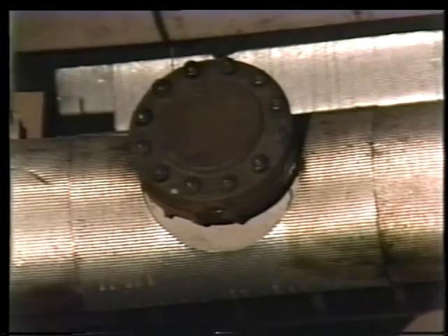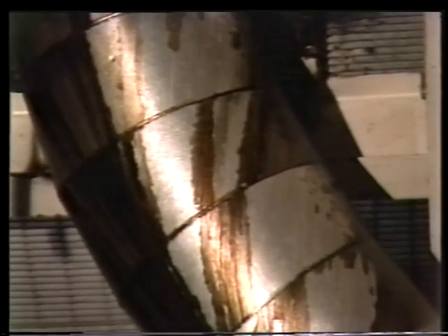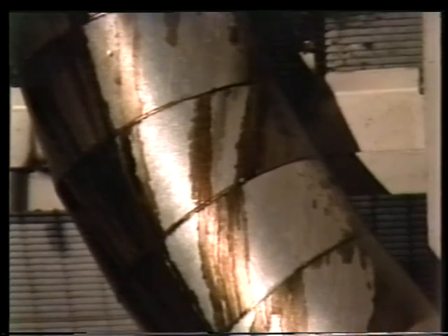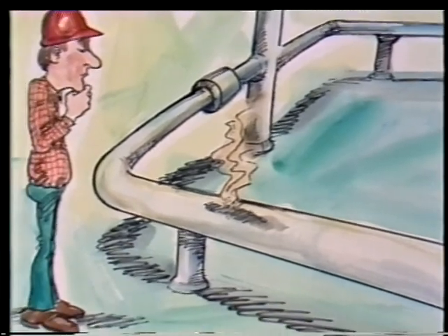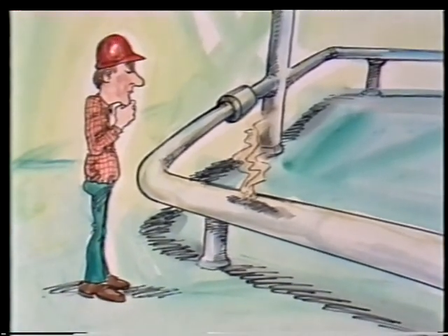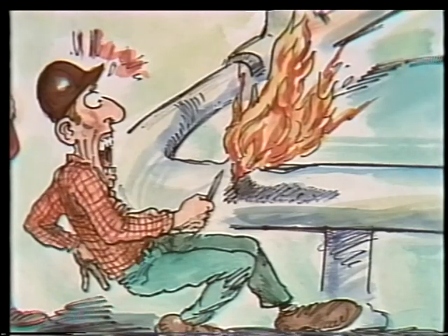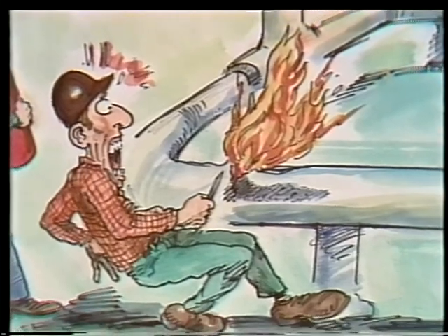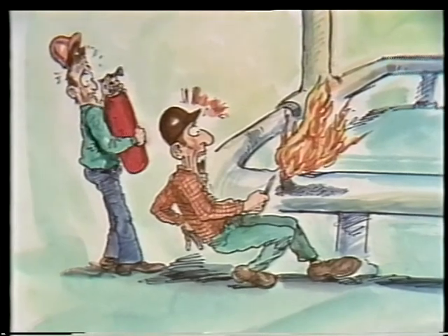When you find a leak, look for the source. Is it water dripping from a pipeline overhead? Or is it oil, possibly from within the insulation? Oil leaks can be a special problem because sometimes the oil catches fire and smolders under the insulation. Smoldering insulation may not be noticed immediately, but when someone cuts into the insulation to repair it and see what's causing a leak, the sudden rush of fresh air to the smoldering insulation can cause a sudden flare-up, and someone could be barbecued.